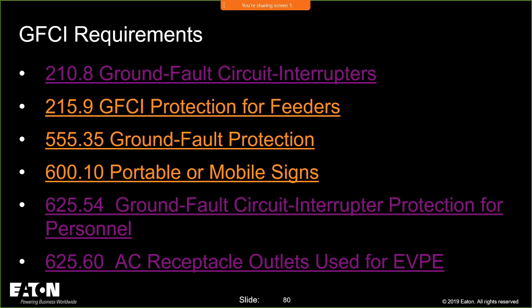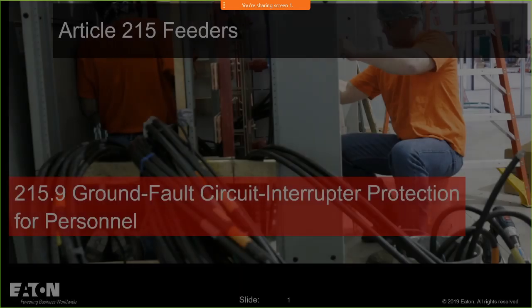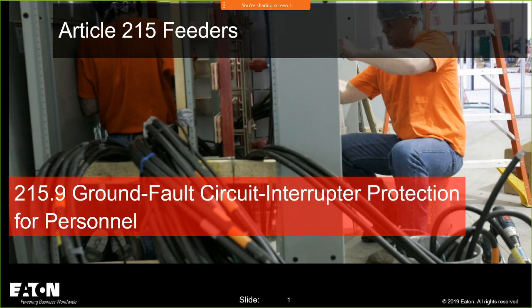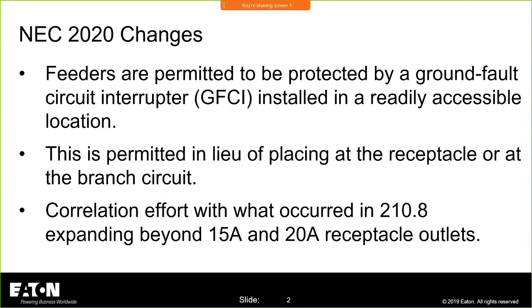All right, I'm going to discard all my changes there, and we're going to take a real quick look at GFCI for feeders. This was a change - ground fault circuit interrupter protection for personnel. Feeders are permitted to be protected by a ground fault circuit interrupter. What happened here relates to the expansion of GFCI. Some people may say, I want to provide the GFCI in a feeder instead of down at the branch circuit or at the receptacle. Say you have a panel upstairs and you just want to feed that whole sub panel with GFCI - you are permitted to do that. This gives you that permission.